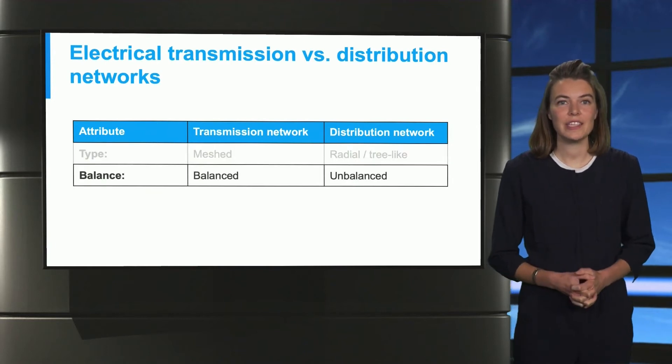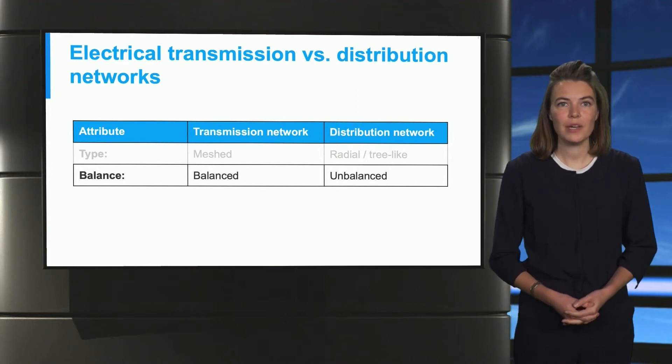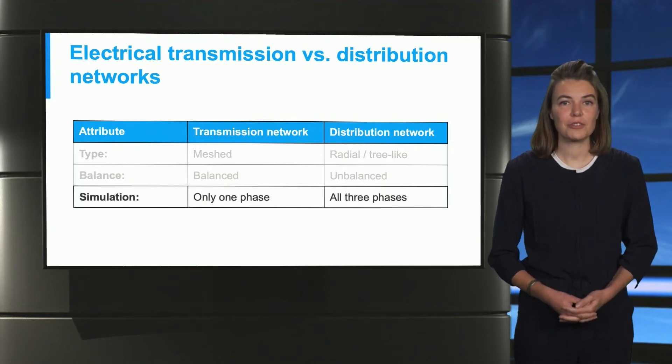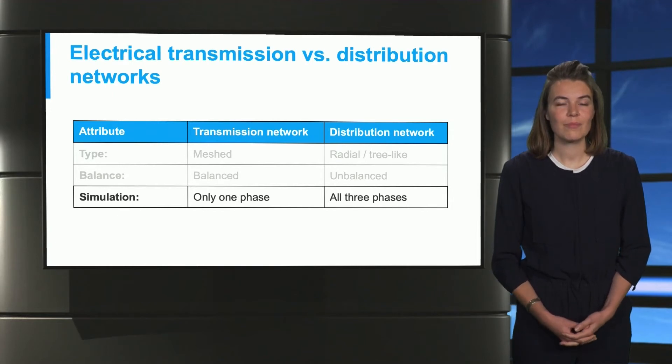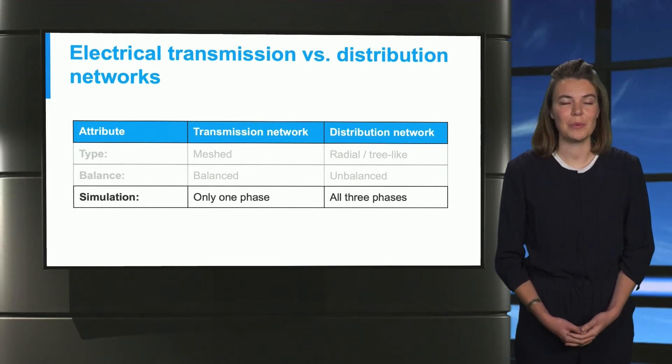Both transmission and distribution networks have three phases, but in the transmission network they are balanced and in the distribution network they are unbalanced. The consequence is that for a transmission network it is sufficient to simulate only one phase, because all phases are in balance. The other phases will simply be a phase shift of the simulated phase. Due to its unbalanced nature, you have to compute all three phases separately in a distribution network.